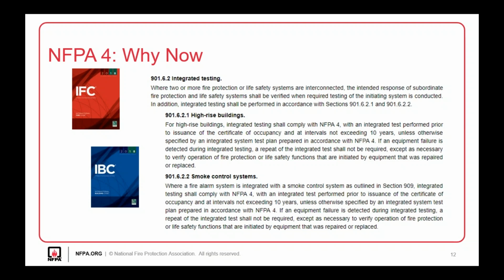Because of that, you want to avoid terms in contracts such as 'includes all required testing,' since those terms put you on the line to cover the cost and time needed for integrated system testing. It's recommended to include a line about additional cost for integrated system testing. That way it starts a conversation with the building owner and design team early on, before you're even brought onto the team, so they can determine whether they need integrated system testing.